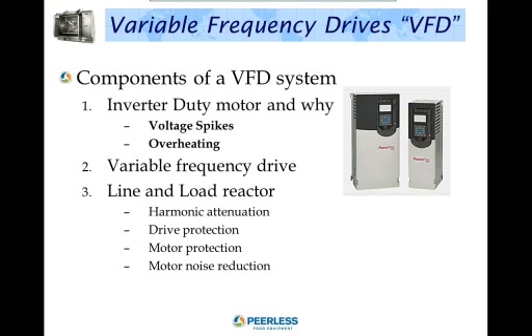Components of the VFD system. We have the inverter duty motors and why you should use them. There are voltage spikes. VFDs generate voltage spikes, and inverter duty motors are wound with inverter grade magnet wire, which has a higher resistance to voltage spikes. The wound motor poles are then dipped in a premium varnish and baked repeatedly. The varnish is built up to a higher thickness than on a standard motor, adding to the increased ability to withstand voltage spikes.